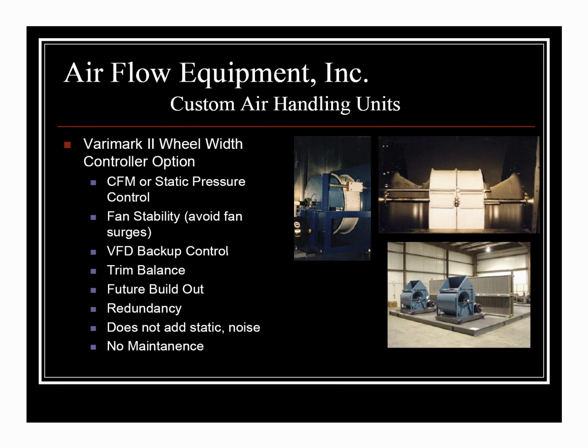What we can do on this is when we slow that fan down, you can move that wheel width controller, take your fan, for example, from 100% width down to 50% width, and then you are able to maintain your tip speed, maintain your static pressure, but yet reduce the CFM of the fan. And so this comes in handy in that type of situation.